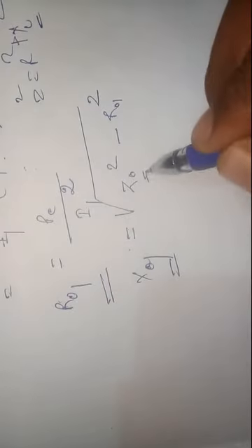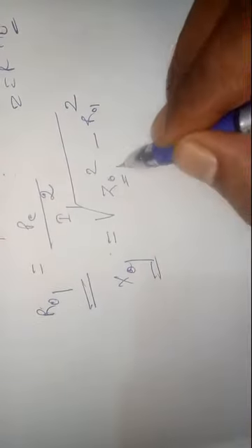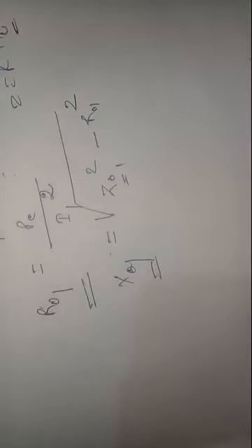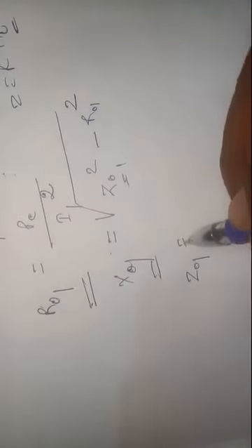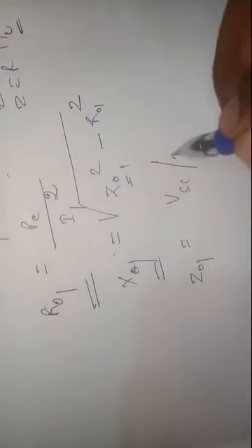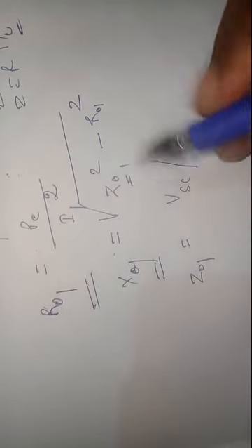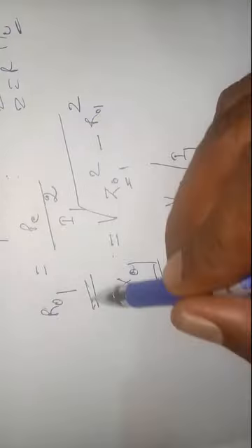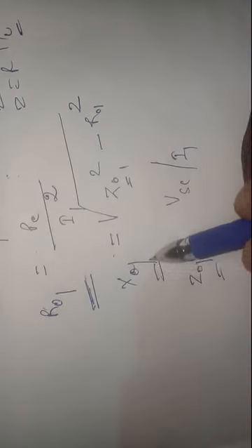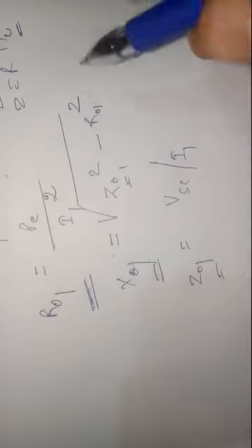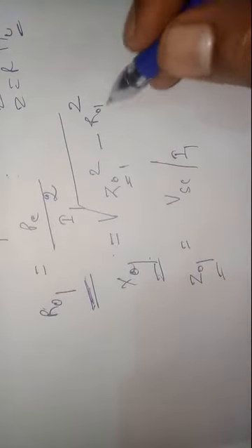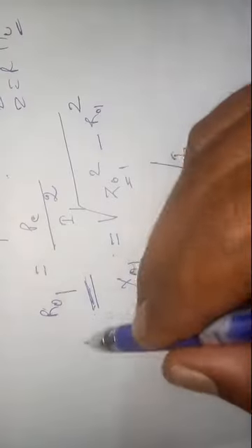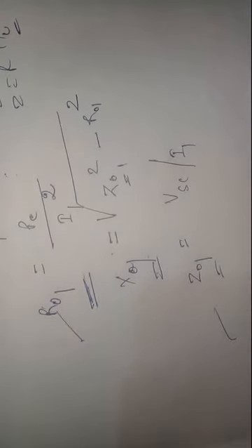So how do we calculate this Z? Z01, the total impedance on the primary side, is the ratio of short circuit voltage by current, since V is equal to IZ. After calculating Z01, and R01 we have already calculated, X01 can be found. So from this test, the copper loss as well as the parameters R01 and X01 can be calculated easily.